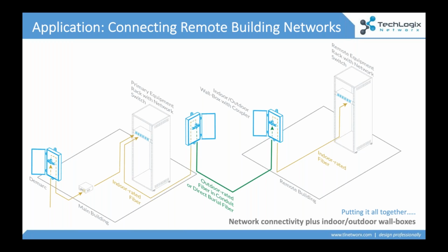Why? Because when we're dealing with this outdoor cabling, it may be direct burial, which is armored. It's really thick. It's kind of hard to pull. It's heavy, right? But it survives a shovel. It survives being buried directly in soil. Well, we want to transition to that indoor riser or plenum rated fiber optic cable where armoring isn't necessary.